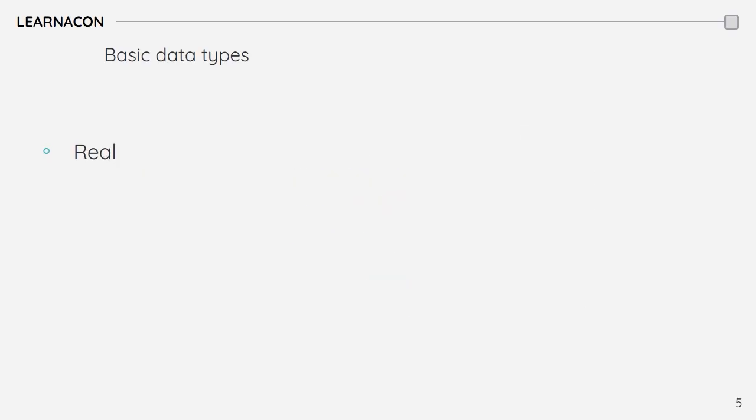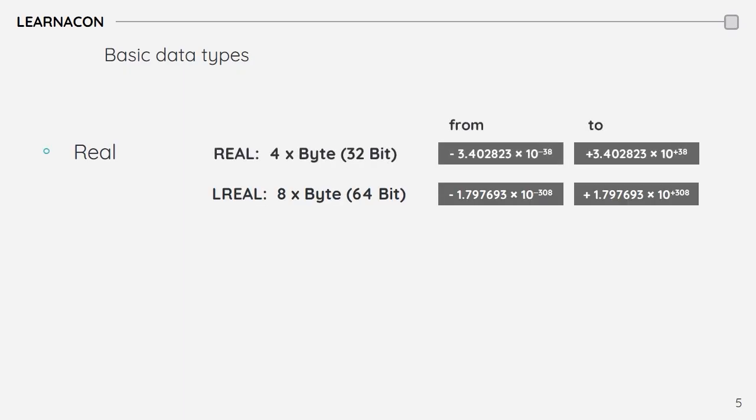In addition to Boolean and integer variables, in some cases, you may need to utilize real tags for floating point decimal variables. For example, to ensure appropriate reading and scaling of real-world variables like temperature and pressure via PLC analog inputs, you may better use tags of type real. In terms of length, real tags could be either 32 or 64 bits.